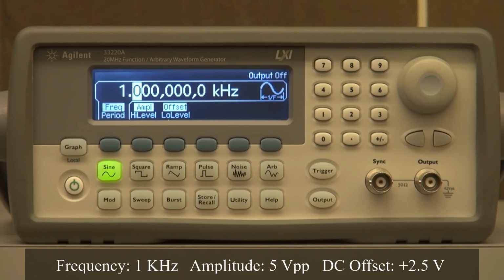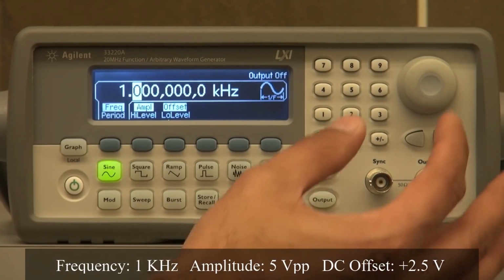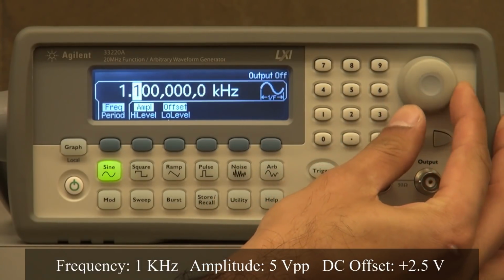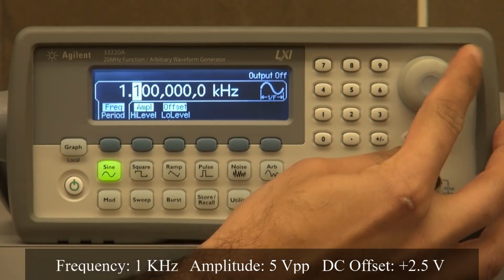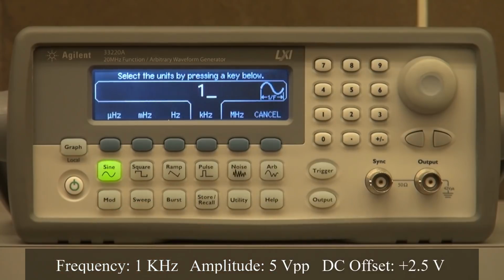We can either modify the frequency of the wave using the knob on the right-hand side of the menu, like so. Note how the highlighted digit over here is changing as I rotate the knob right and left. Or, in order to make larger changes, we can key in what we desire as our output frequency onto the numerical pad. I am now going to press the digit 1, which brings up this menu.